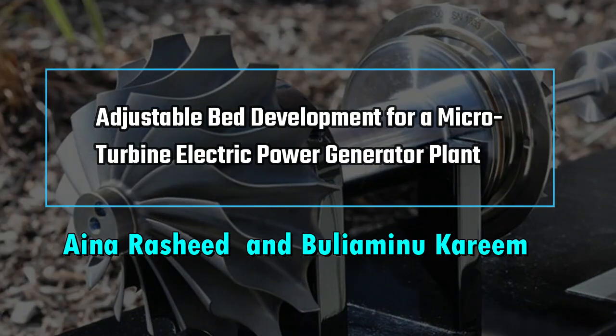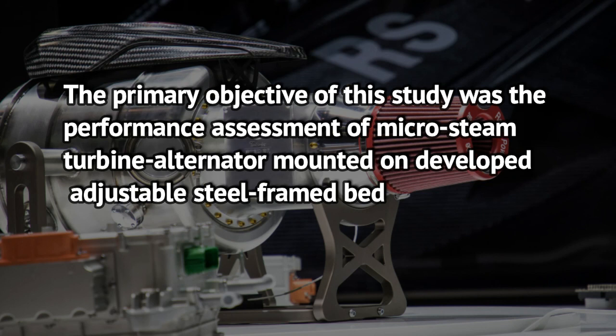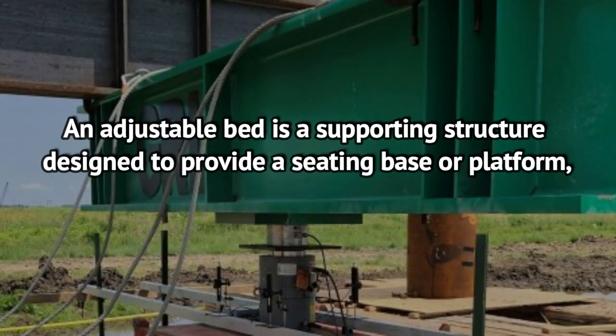Adjustable Bed Development for a Micro-Turbine Electric Power Generator Plant, by Aina Rasheed and Buliaminu Kareem. The primary objective of this study was the performance assessment of a micro-steam turbine alternator mounted on a developed adjustable steel-framed bed, when their shafts were either axially connected with flexible flange coupling or transversely connected with sets of belt and pulley power transmission. An adjustable bed is a supporting structure designed to provide a seating base or platform for a 5.0 kW micro-steam turbine generator plant prior to its mounting on a block-type concrete foundation.